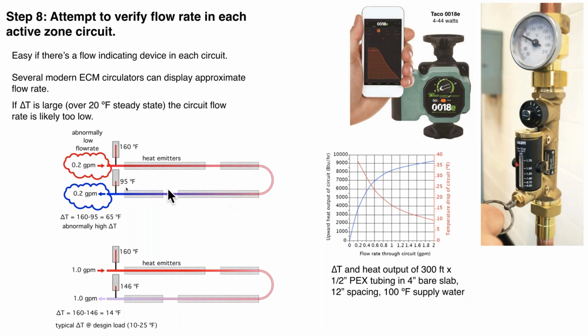We're going through some kind of a circuit and we're going in at 160, we're coming back at 95. So our delta T is 65 degrees. Now that is way beyond what a reasonable hydronic distribution circuit should be operating at. And typically that's the underlying cause of insufficient heat delivery. Something is causing that flow rate to be much lower than it needs to be.